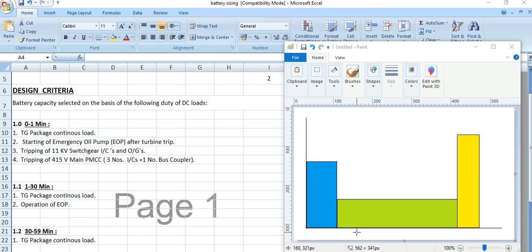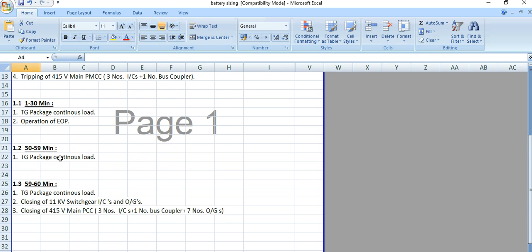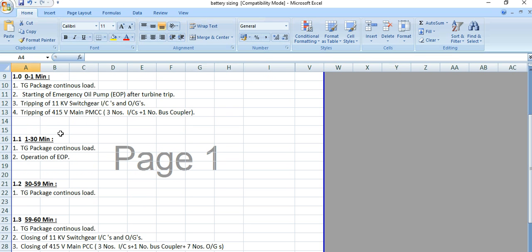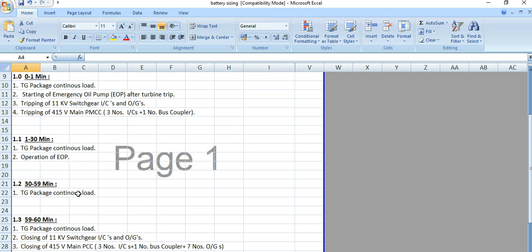This is the load model — how the battery needs to supply the loads. There are four sections: the first is 0 to 1 minute, next is 1 to 30 minutes, then 30 to 59 minutes, and the last is 59 to 60 minutes. In some cases, we can merge the 1-to-30 and 30-to-59 minute sections into a single step, making it three steps total: step 1 (0-1 min), step 2 (1-59 min), and step 3 (59-60 min).